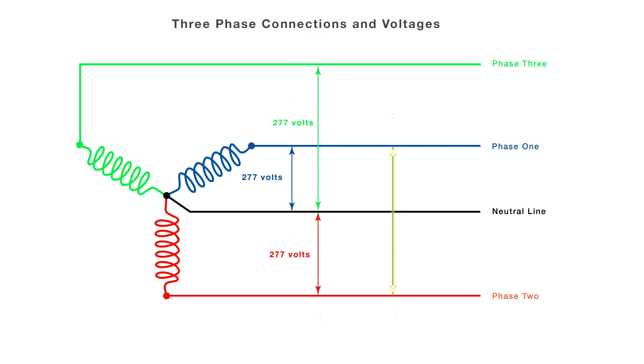First, phase one to phase two reads 480 volts, which is phase one to neutral, 277 volts, times root three, or 1.73. 480 volts is read phase one to phase three, and the same voltage phase two to phase three.